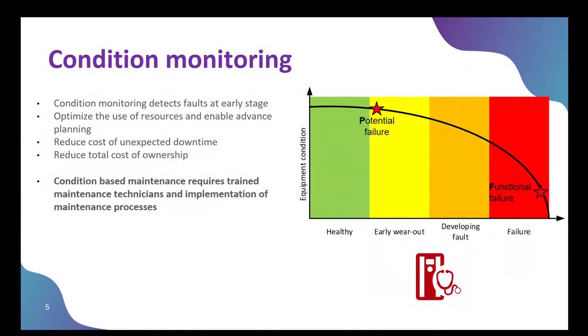The change from the P point, which is the potential failure, to the functional failure, the F point. And that is because degradation doesn't happen immediately. It happens in time. And then if we monitor this condition, we can detect a change and trigger a maintenance process. By doing this, we can detect faults at early stage, optimize the maintenance, and reduce the cost of unexpected downtime.